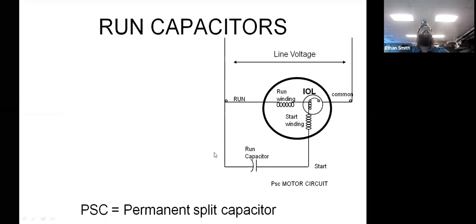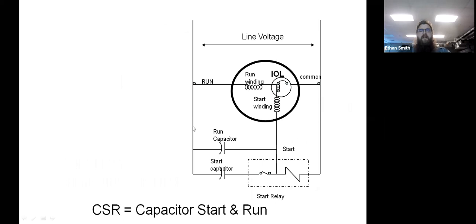So let's talk a little bit more about capacitors. We dealt with this one, guys. This is a run capacitor. That's the motor we were just working with. It's just using that capacitor there to put that start winding slightly out of phase just to increase the efficiency of the motor a little bit. So this capacitor is always in circuit. The other time we see capacitors in use is in an application like this, where this is a capacitor start and run. So we have a run capacitor, just like we had before, but then we have this extra capacitor down here, and this is a start capacitor.